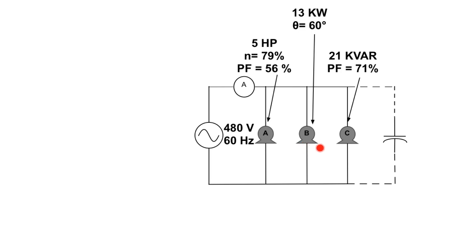Over on this guy here, it's got 13 kilowatts of true power with a phase angle of 60 degrees. And over here, it's got 21 kVAR of inductive power, wattless power being used with a power factor of 71%. And this little guy here, that's the power factor capacitor that we're going to be putting in there to fix it all up.